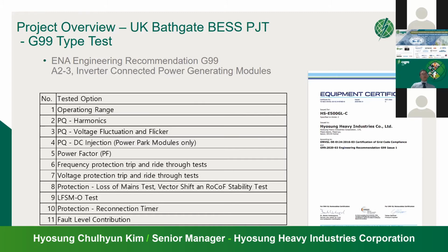This test consists of the following: operating range for PCS and harmonics, voltage fluctuation and flicker, DC injection, power factor, frequency protection trip and ride-through test, voltage protection trip and ride-through test, protection loss of mains test, vector shift and ROCOF stability test, limited frequency sensitive mode test (LFSM-O), protection and reconnection timer test, and fault level contribution.